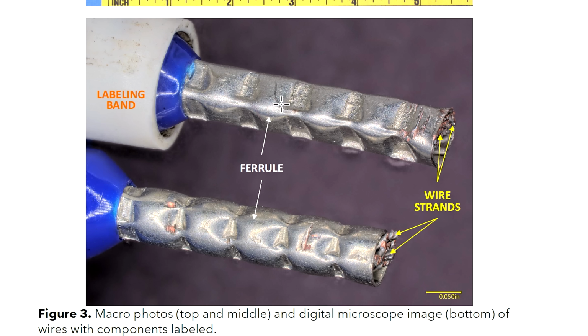On your ferrule, it's supposed to have these crimps, with your wire strands inside. Once it's been inserted into one of these terminal blocks, over the years it'll leave this indentation, so that's your first mark. It should leave a single straight gouge there, and possibly these other two points of connection. That's how you know it had a good connection.